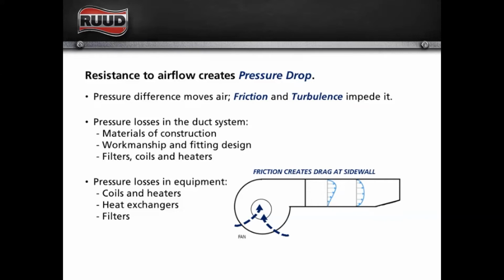If, as part of a service call, a change out, whatever you're doing, part of that is to upgrade IAQ, right? If you're going to add some filtration, if you're going to add a UV light, if you're going to add anything to that airstream, you need to make sure that you're not causing issues with your static pressure. And if that's the case, you might need to expand or add some ductwork. Not saying don't sell IAQ products at all. I'm just saying if you do, you might have to factor in adding some ductwork.